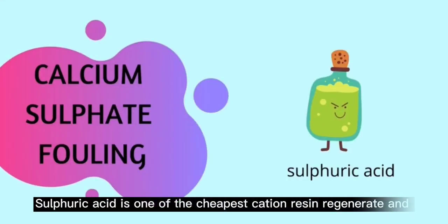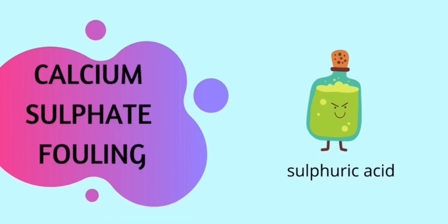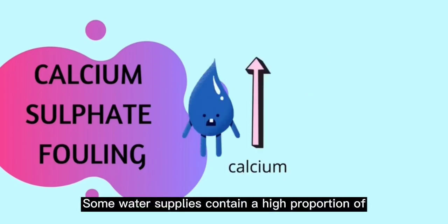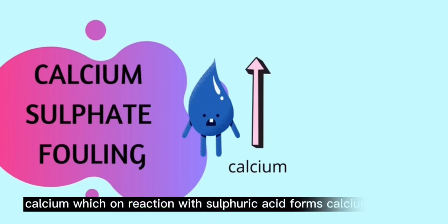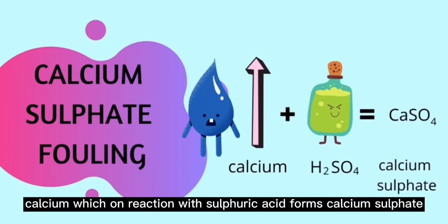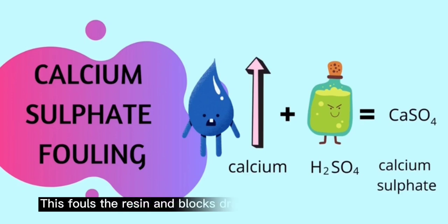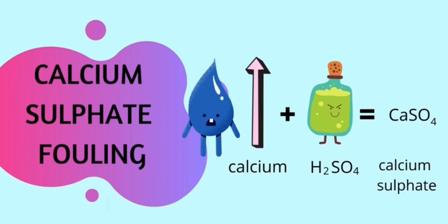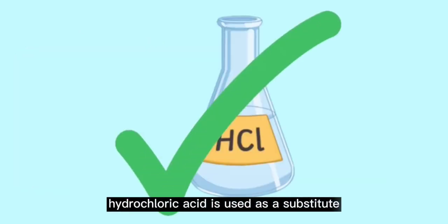Fourth, it may also cause calcium sulfate fouling. Sulfuric acid is one of the cheapest cation resins to regenerate and is widely used. Some water supplies contain a higher proportion of calcium, which on reaction with sulfuric acid forms calcium sulfate. This fouls the resin and blocks drain pipes with a build-up of scale. Under such circumstances, hydrochloric acid is used as a substitute.